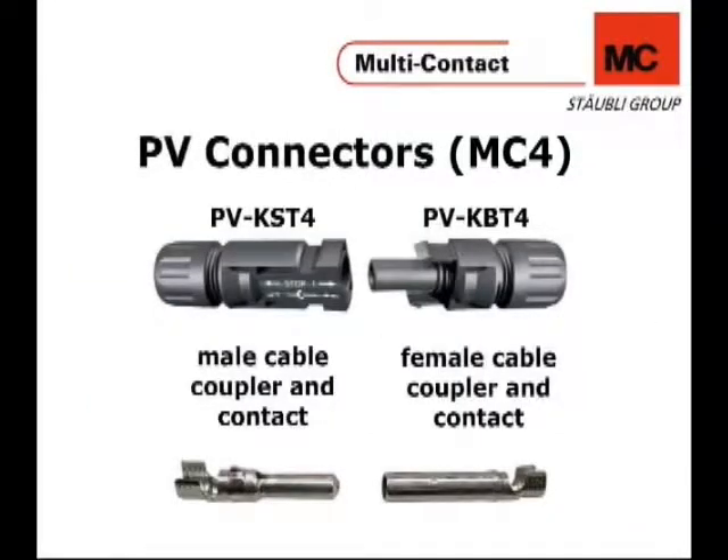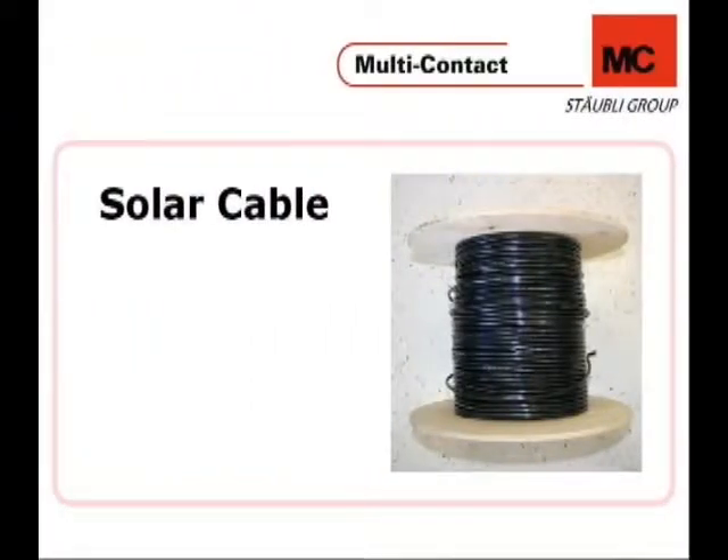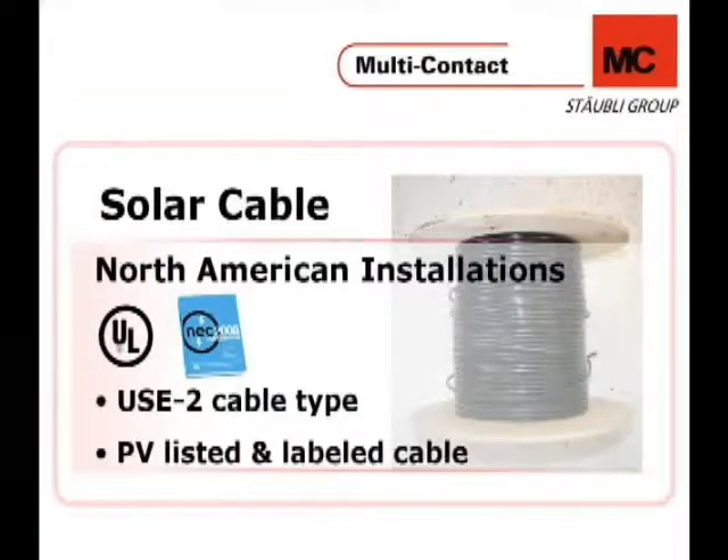Along with the tools, you will need these PV connectors and contacts for assembly. For North American installations, in accordance with UL and the National Electric Code 2008, you are permitted to use single-conductor USE-2 cable type or single-conductor cable listed and labeled as PV. For all other countries, please refer to your product safety testing and certification organization as well as to your electric code.